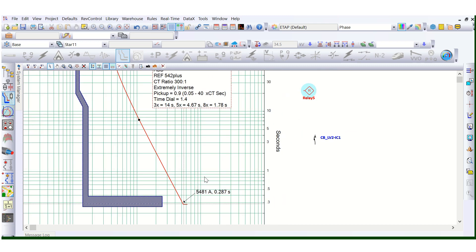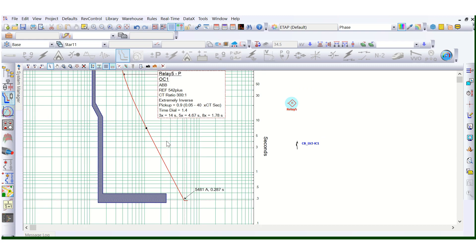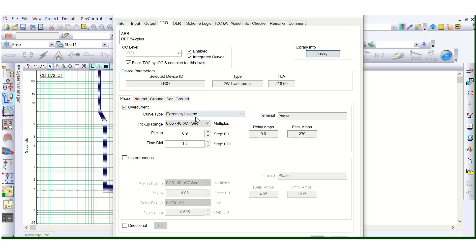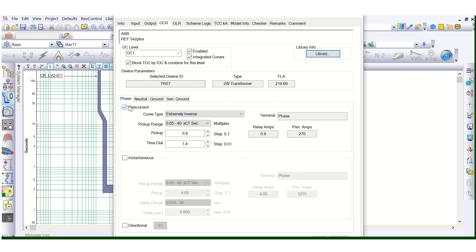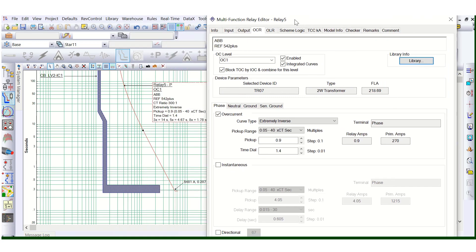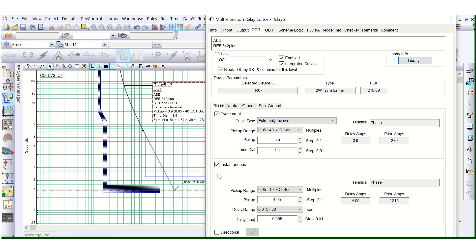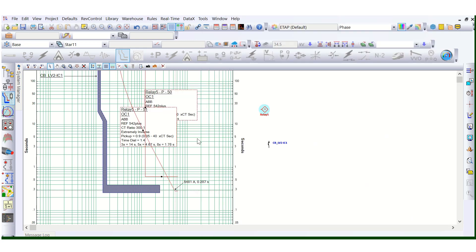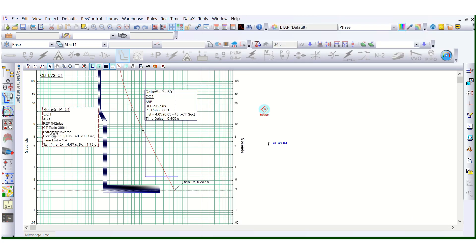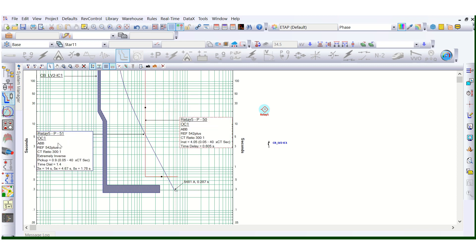Now that we've understood the IDMT characteristic, let's go back to the relay settings and enable the 50 setting. If I enable this 50, you can see there are now two separate curves generated in the TCC curve — one is 51 and the other is 50.